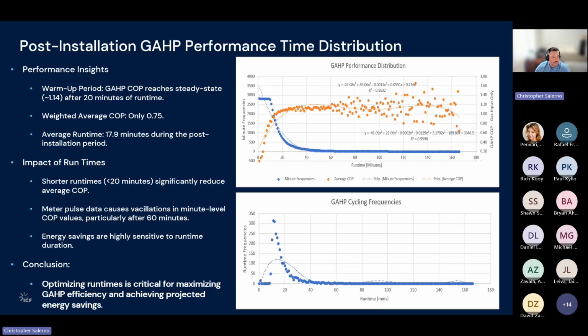And so what we have is the impact of runtimes, which is less than 20 minutes, really significantly reduced the COP. And so the metering pulse causes the vacillations in the minute pulse data after 60 minutes, and energy savings are highly sensitive to runtime duration. So it's really, really critical to maximize performance of this and keep it running based on the design and properly sizing these things to be able to keep them running and base loading them. And so that they're not just cycling up till about 20 minutes and turning off. And so these units really need to run for at least 20 minutes to be able to reach that optimal performance and then keep running.